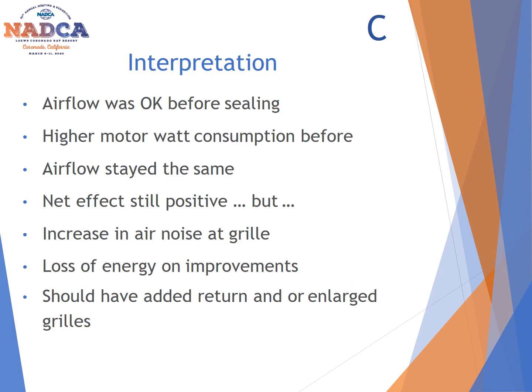The airflow before all the improvements were made was actually okay, because you still had 1,000 CFM flowing into the home. But the problem is the motor was working harder because it had to run longer before all these improvements were done, because it was pulling air from the attic that had to be conditioned before entering the house. So even though the airflow stayed the same overall, the net effect was still positive. The issue they had is they had more airflow coming from the return, so it created some noise, which led them to having to increase the return itself. But the biggest benefit is you had lots of improvements in overall energy efficiency, because the system did not have to work as long or as hard to condition the air like it did before. So overall, it was an improvement for them.